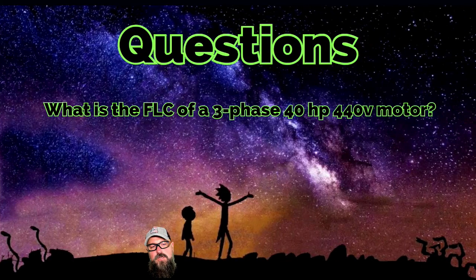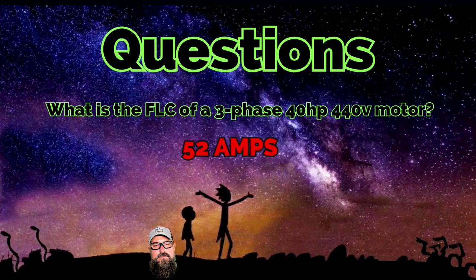So let's go ahead and go to the next question. What is the full load current of a 3-phase, 40 horsepower, 440 volt motor? Go ahead and pause, look up the answer. 52 amps is the answer.